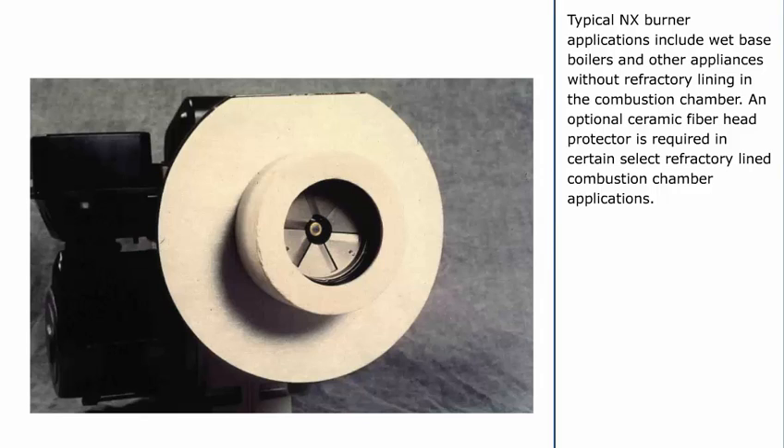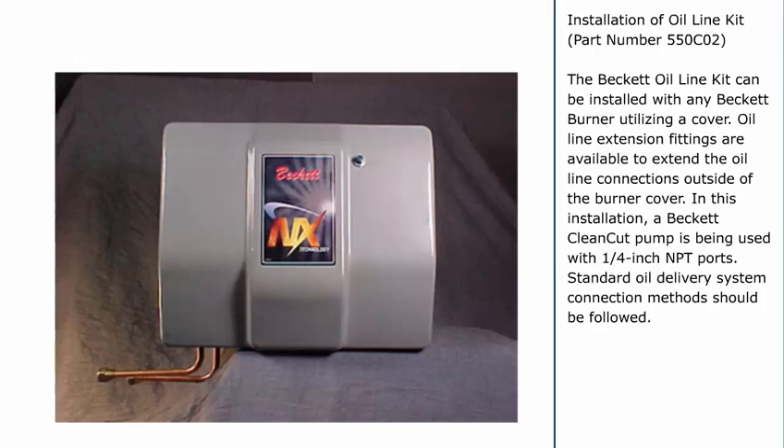Typical NX burner applications include wet-based boilers and other appliances without refractory lining in the combustion chamber. An optional ceramic fiber head protector is required in certain select refractory-lined combustion chamber applications. For installation of the oil line kit, part number 550C02, the Beckett oil line kit can be installed with any Beckett burner utilizing a cover. Oil line extension fittings are available to extend the oil line connections outside of the burner cover. In this installation, a Beckett CleanCut pump is being used with 1/4-inch NPT ports. Standard oil delivery system connection methods should be followed.